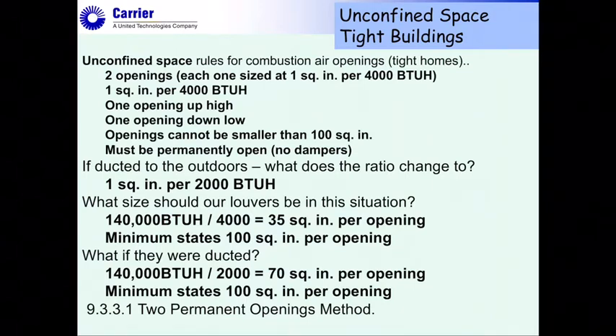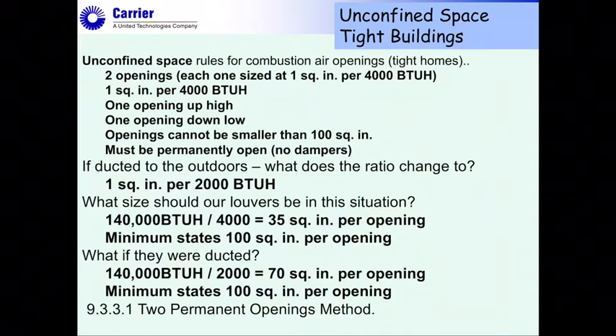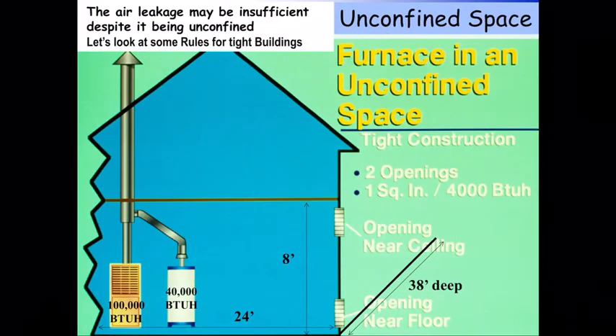Additional rules: no opening can be smaller than 100 square inches, no dimension less than 3 inches, and the openings must be permanent — no manual dampers that someone could close. If the openings are ducted to the outdoors, the ratio changes to one square inch per 2,000 BTUs, which means you need double the area.